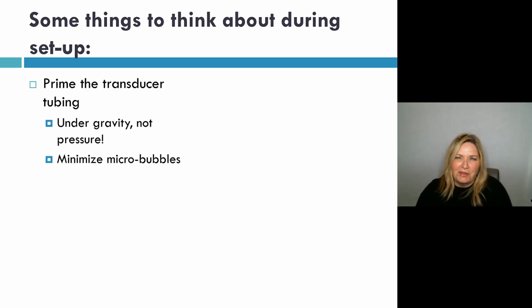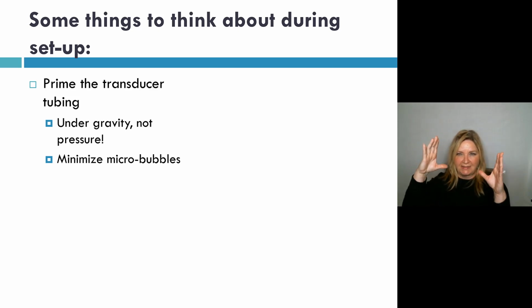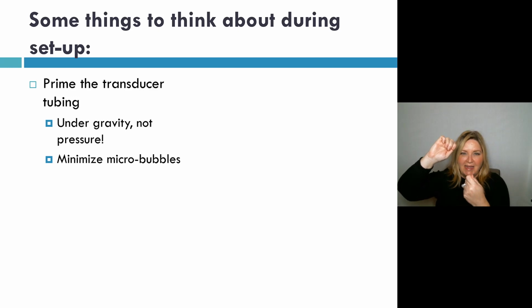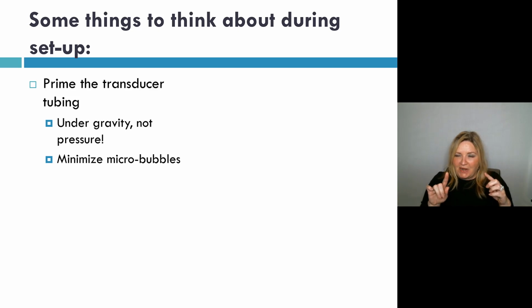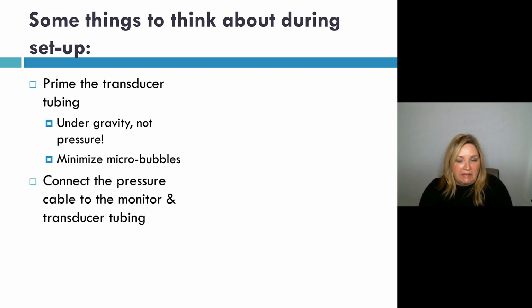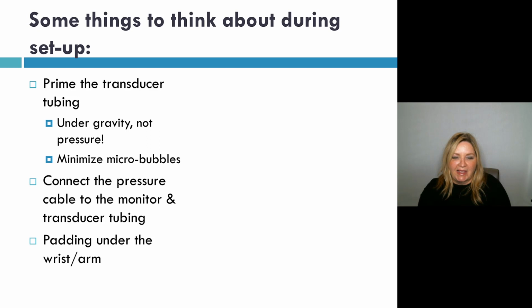All right, so some other things to think about during setup is you want to prime your transducer tubing. Remember, you're going to be using a very specific non-compliant stiff tubing, and you'll use your saline bag and spike it with this tubing. Then you want to prime the tubing, but do it under gravity and not with the pressure bag inflated. If you prime your tubing with the pressure bag inflated, you can introduce a lot of microbubbles, which can cause a lot of problems down the road. Then make sure you connect your pressure cable to the monitor and tubing, and I'll show you what that looks like as well.